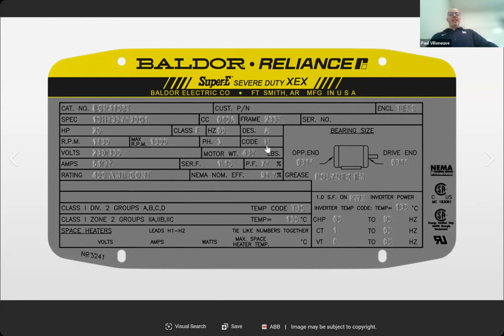Three-phase. This is the thing that tells us the inrush code. This is a code, and we'll look at that more in a minute, but it tells us how many kVA per horsepower you need to start the application. So it's just a way of calculating the approximate amount of inrush. And then it's dual rated, which a lot of motors are. 230, 460 works really well.